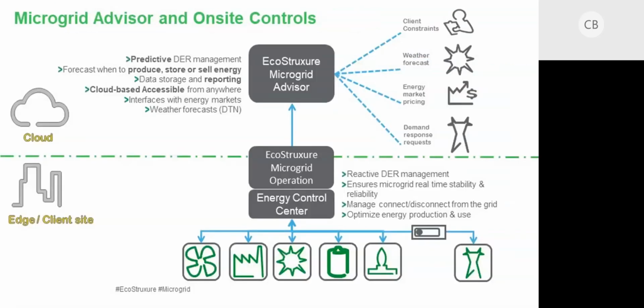So the challenging part now is, since we said we have all these capabilities of maybe self-generation and battery energy storage system, including the batteries attached to the UPS, when do I charge? When do I discharge? How far do I discharge? When you think about the UPS energy, as Mark mentioned, the batteries on the UPS are our insurance policies, right? So if we design the system for 10 minutes, that's the amount of backup time we want. If we do have backup generators, we may not need the full 10 minutes.